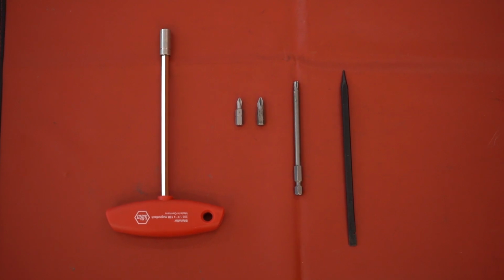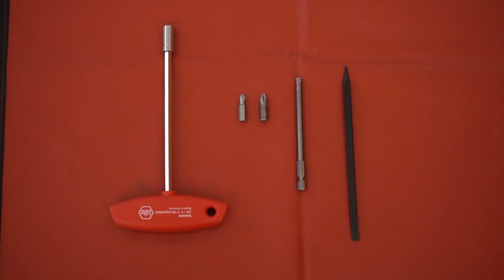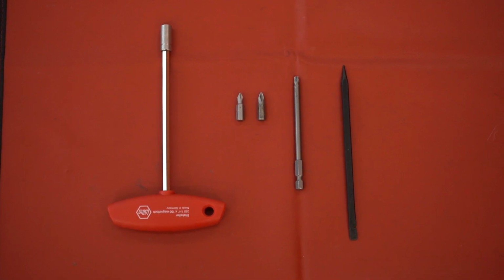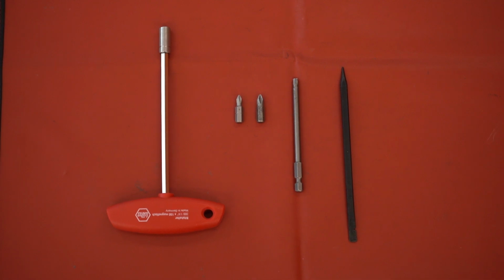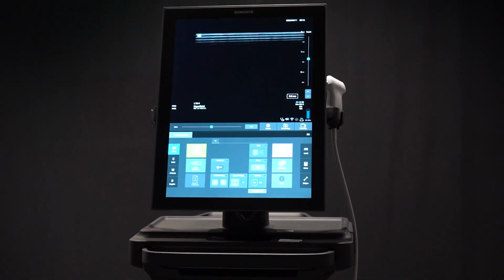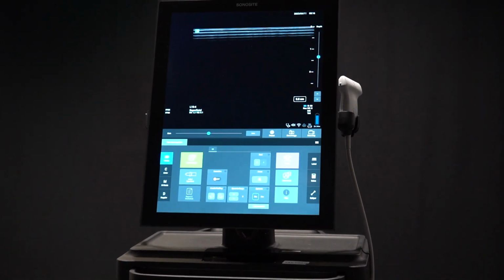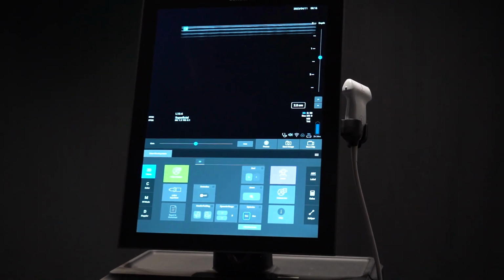This service of the Sonosite ST will require a prying tool, a magnetic bit driver, number 1 and number 2 Phillips head bits, and 3mm and 4mm hex head bits. Torque all fasteners to 5.5 inch-pounds, 0.62 Newton-meters unless otherwise specified.